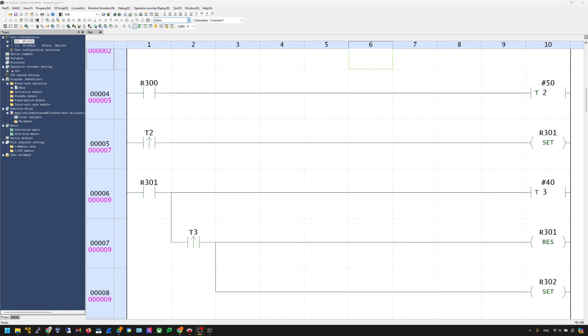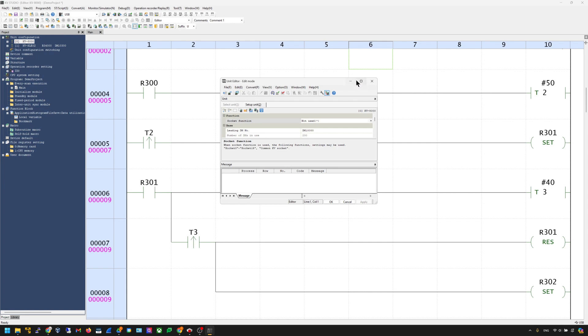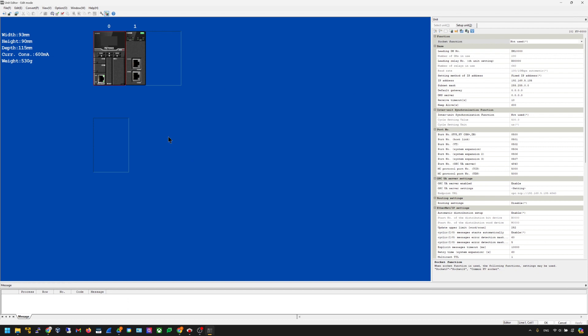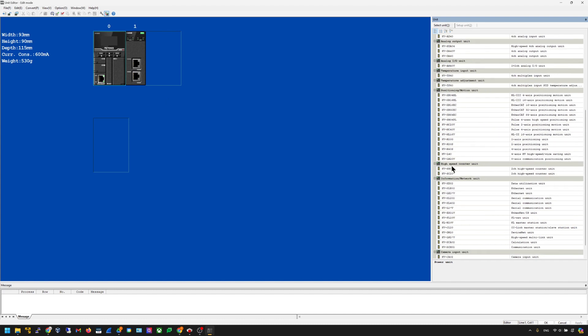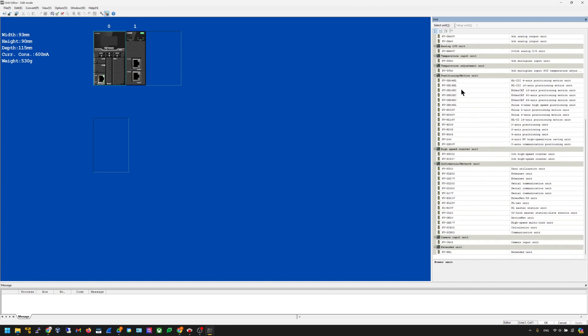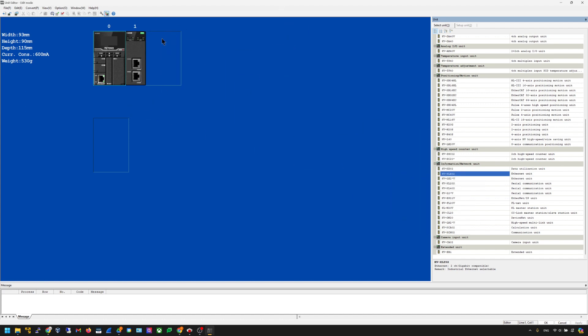First we will configure the KEYENCE side. We'll open KV-Studio and make sure that you change your KV-Studio mode to Editor. Then we can open KV-8000, and there is a communication editor screen that allows you to make the configurations. In this project I already configured my hardware, but I'll show you how to do this. You can go to select the EtherCAT unit, then scroll down and find a unit called KV-XLE02. Just drop it into your configuration to add it to your network.